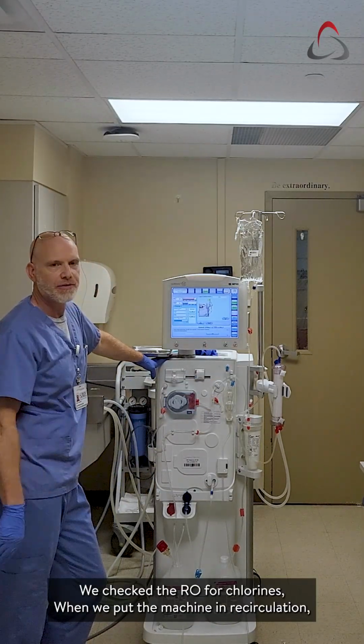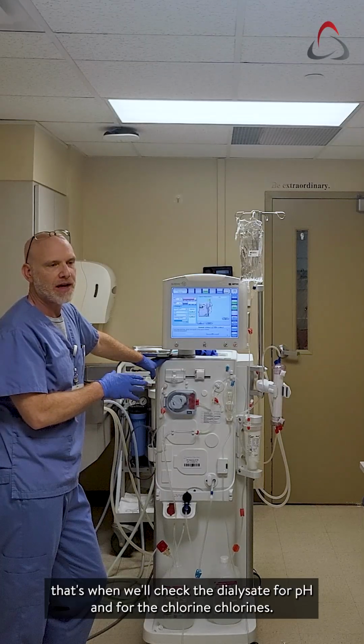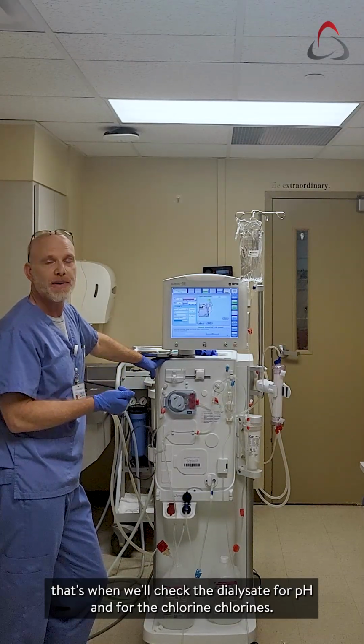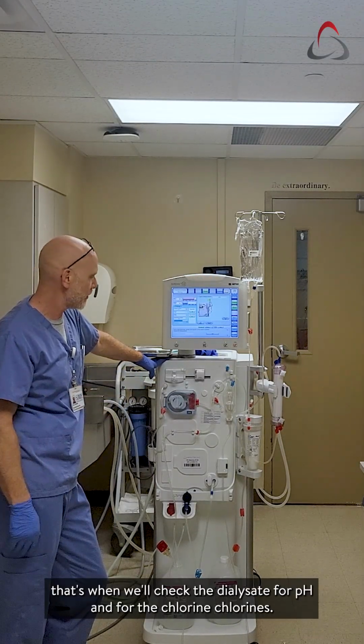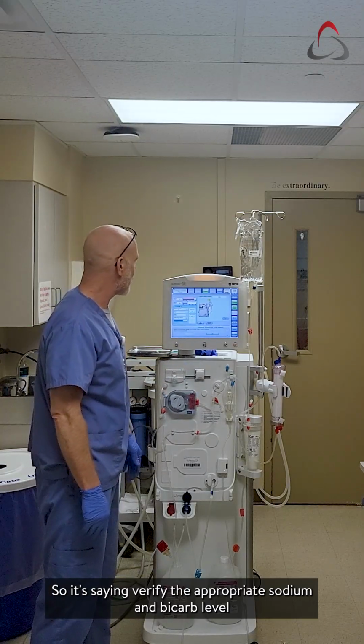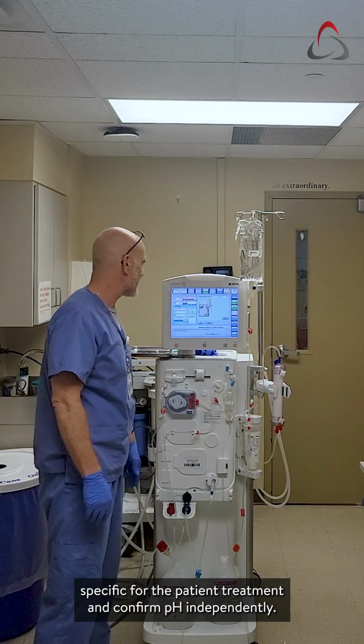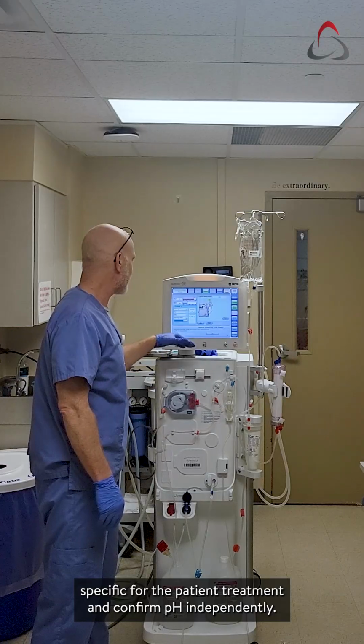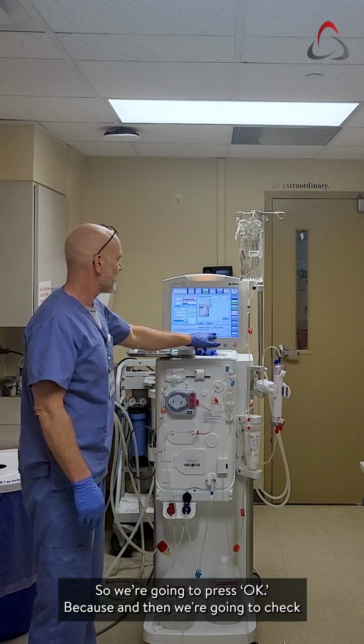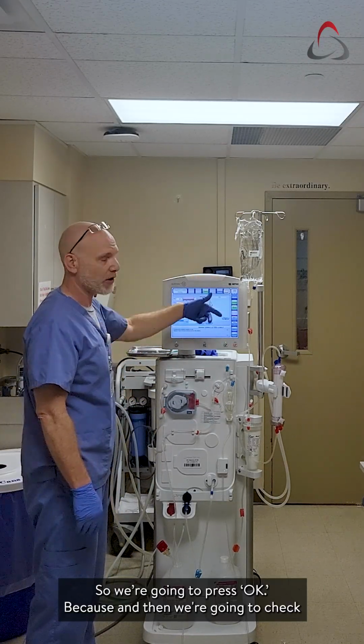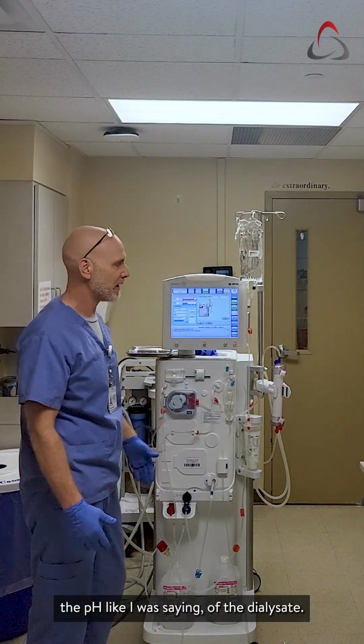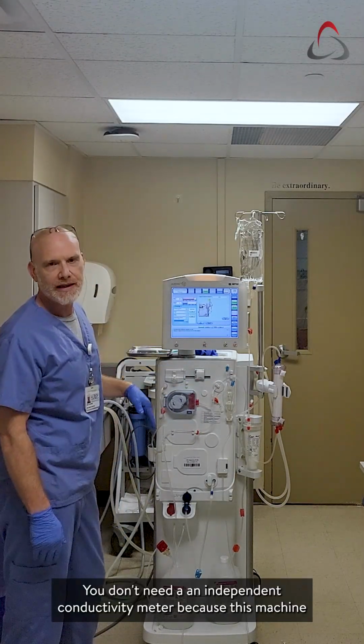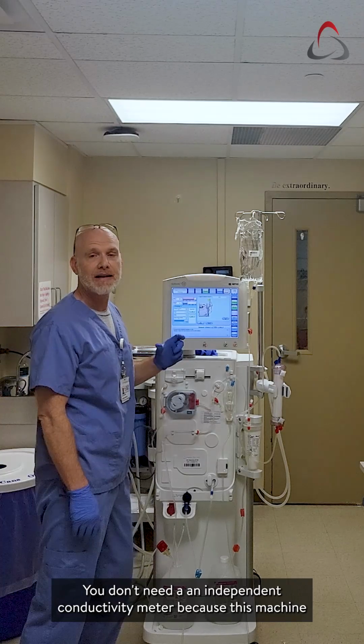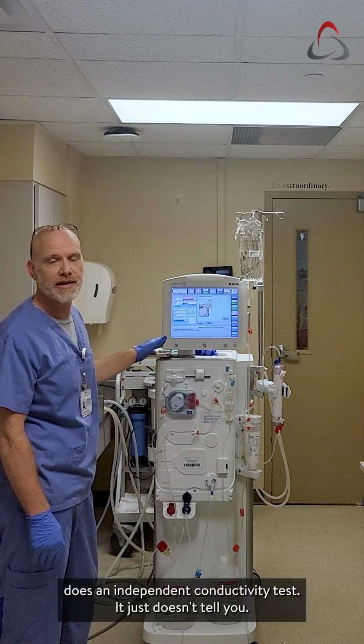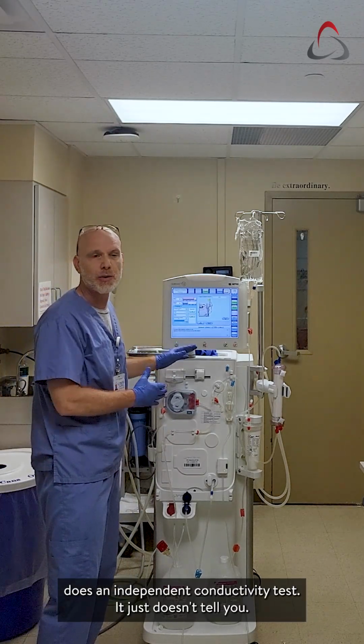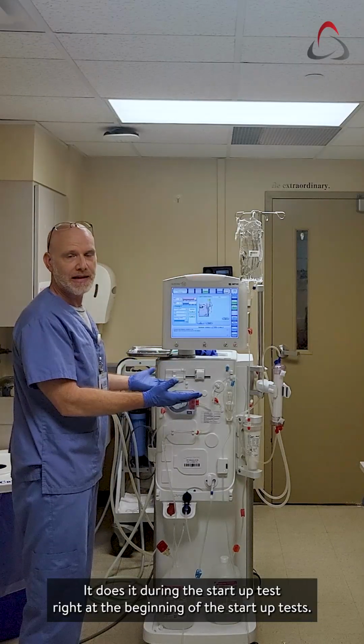When we put the machine in recirculation, that's when we'll check the dialysate for pH and for the chloramines. So it's saying verify the appropriate sodium and bicarb level specific for the patient treatment and confirm pH independently. So we're gonna press OK, and then we're gonna check the pH, like I was saying, of the dialysate. You don't need an independent conductivity meter, because this machine does an independent conductivity test. It just doesn't tell you. It does it during the startup test, right at the beginning of the startup test.